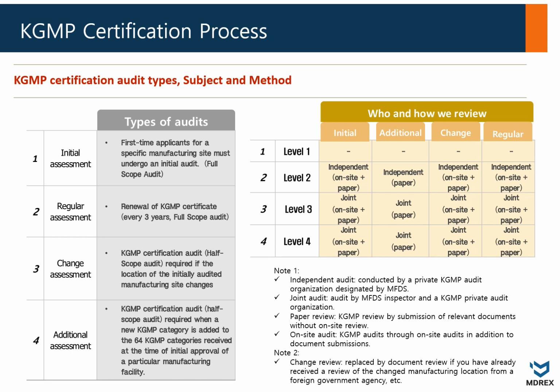Regular assessments occur every 3 years for manufacturers who have already received KGMP certificates. Like the initial, regular assessments also involve a full-scope review. Change assessments are required when there are changes or expansions to the location of a manufacturer who has previously undergone an assessment. Finally, additional assessments may be verified when there are other specific requirements beyond the initial or change assessment. Initial, regular, change, or additional assessment determines the type of assessment, standalone or joint, and whether it's conducted on-site or through document review.